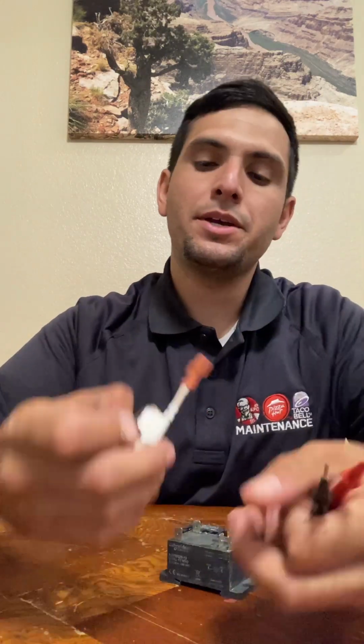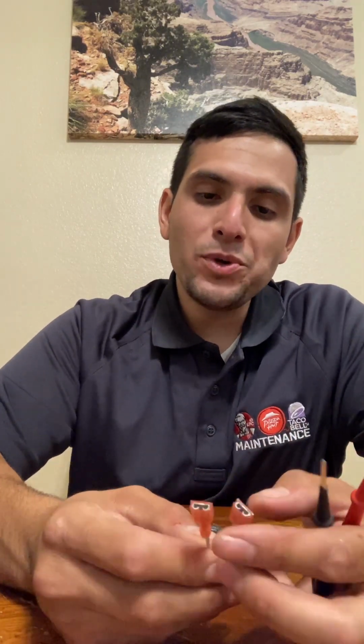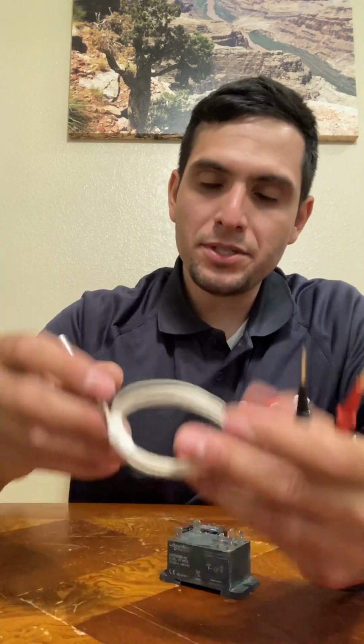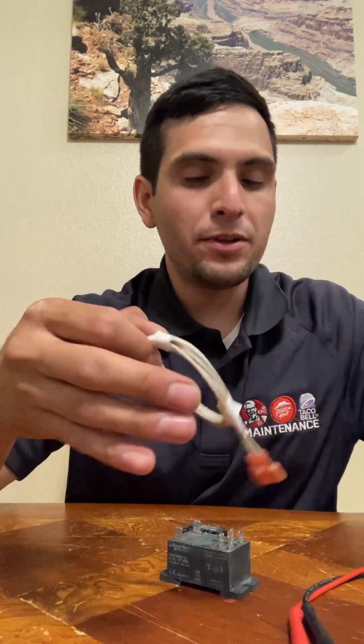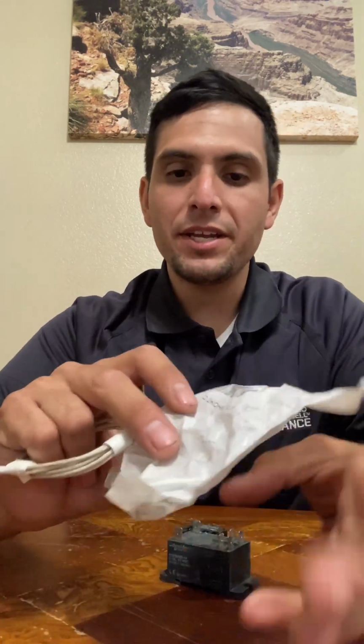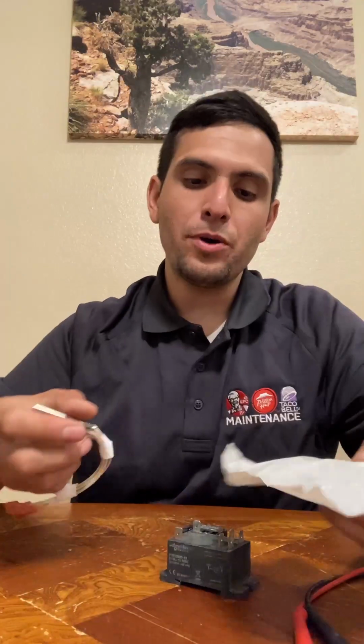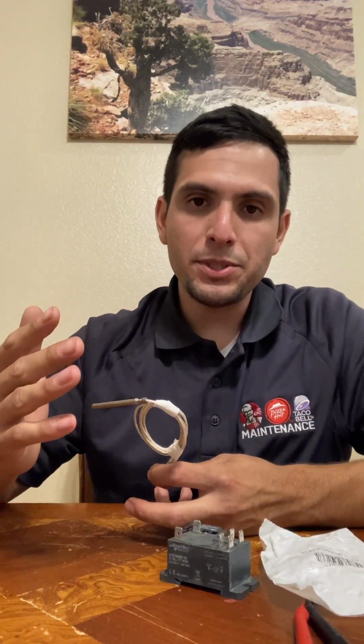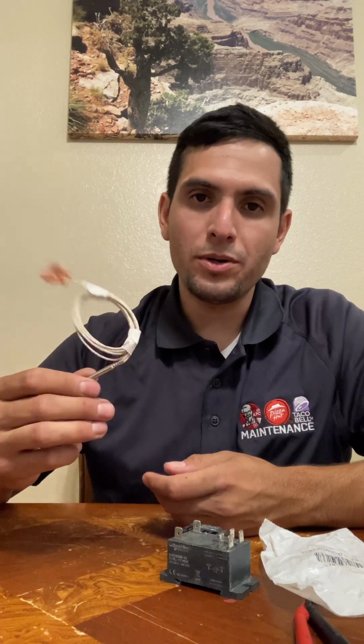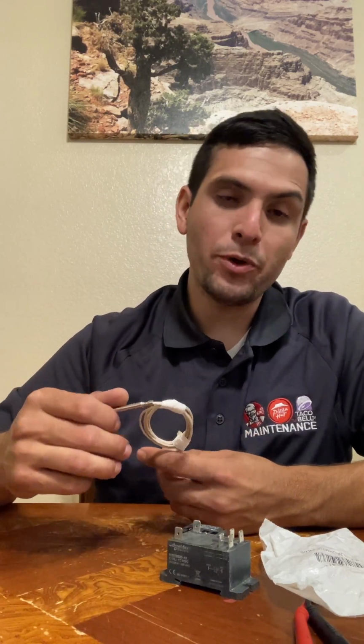So usually what I'll do is check the probes, and it really doesn't matter which one you start with. So if you look on a new package, you'll see a rating for any probes that you buy. It doesn't have to be this piece of equipment. Any heat sensor or probe is going to have a rating. So like this one, it says 2K. So at room temperature, it's going to be around 2,000 ohms or 2,100 ohms. That's around room temperature.